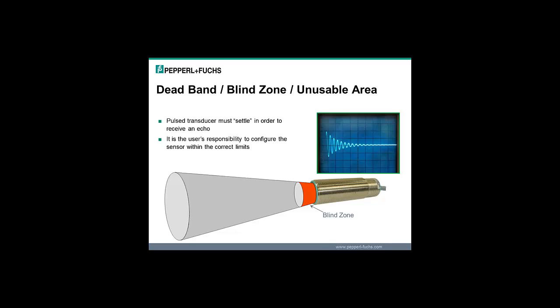You can get multiple echoes where the sound pulse goes from the transducer to the target, back to the transducer, back to the target, and back. In that period of time, the transducer will have finally settled down and it thinks the target's twice as far away as it really is. So the sensor doesn't know. If it's in the blind zone, all bets are off. So the customer must know there's just no way he should be banking on using that blind zone area for his detection. You've got to be from the end of the blind zone out.